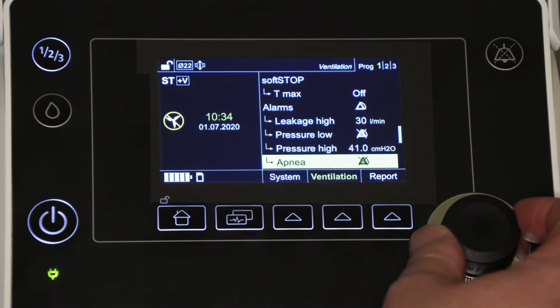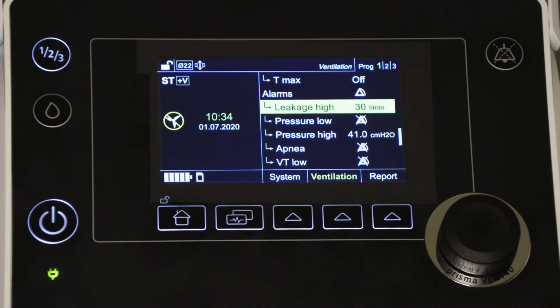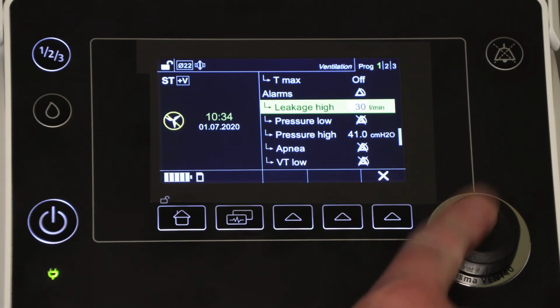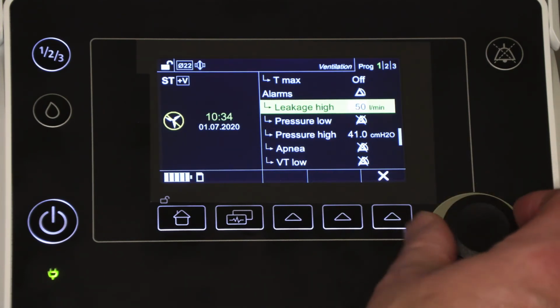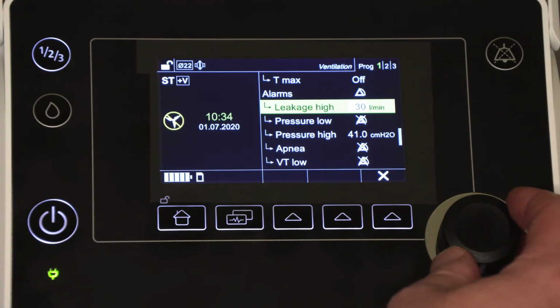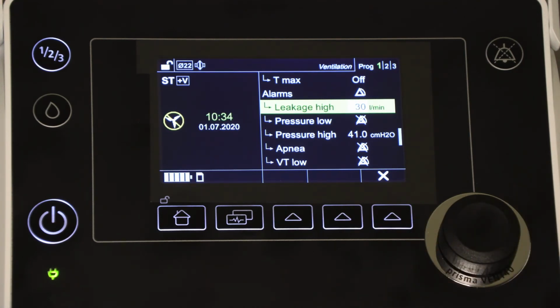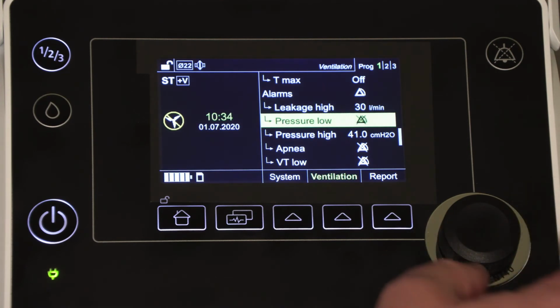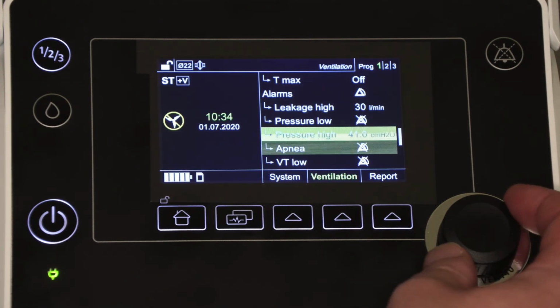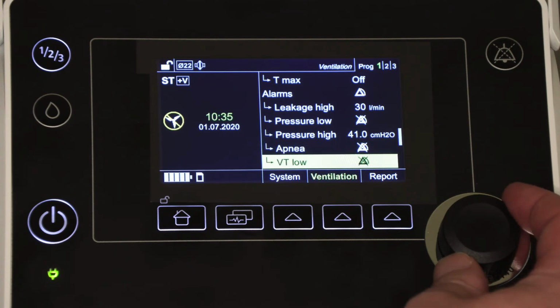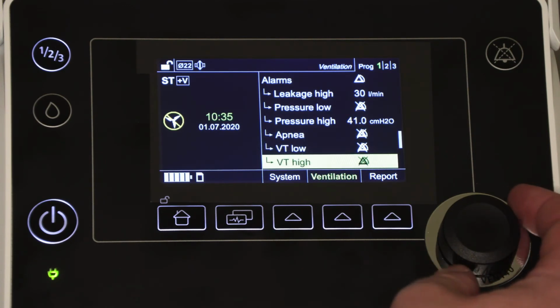Next, we're on to alarms, which can be turned on to give an audible alarm for things that may happen during therapy that you want the user and/or the clinical staff to be aware of. The high leak alarm, as explained earlier, warns of excessive leak from the patient's mask or breathing circuit. It should be set to a value you're happy with so that an alarm will sound when leakage exceeds that value.